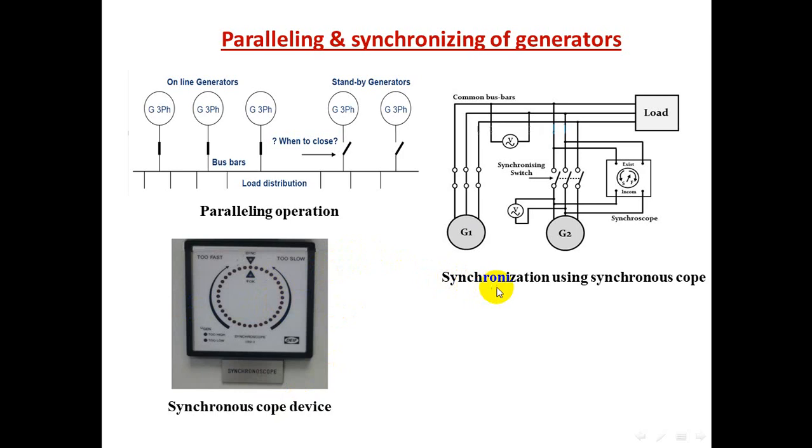And then only when those four conditions are simultaneously present and the standby generator is running at synchronized speed, and the voltage is adjusted in phase, it means that it's synchronized. Closing the main loading breaker can then be done. The synchroscope is a device that checks the phase angles of the two sources during the process of synchronizing.